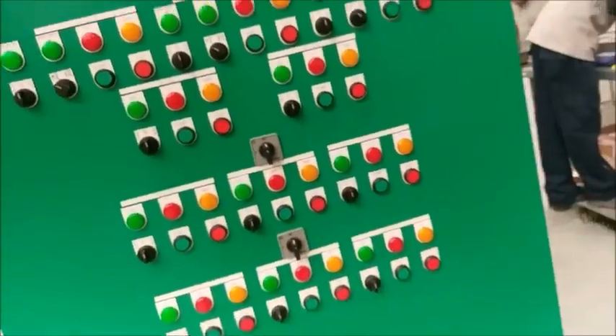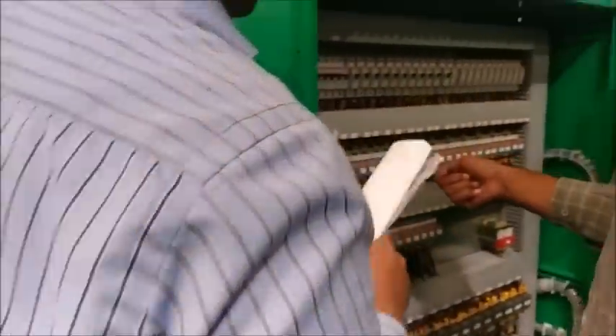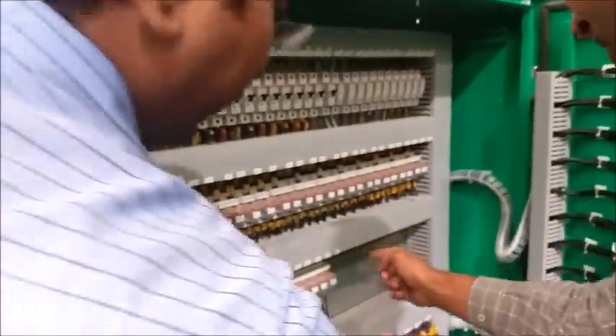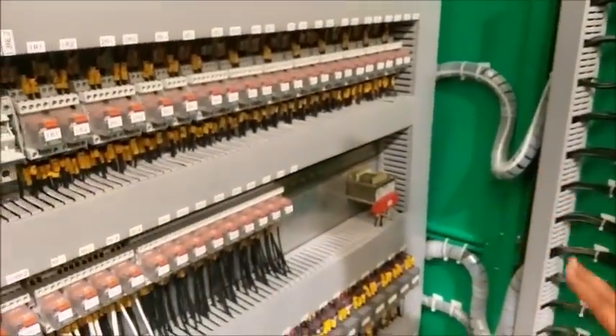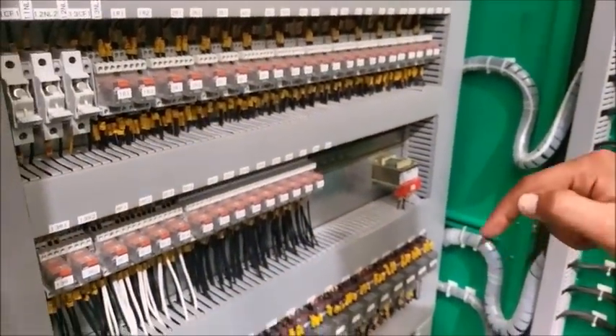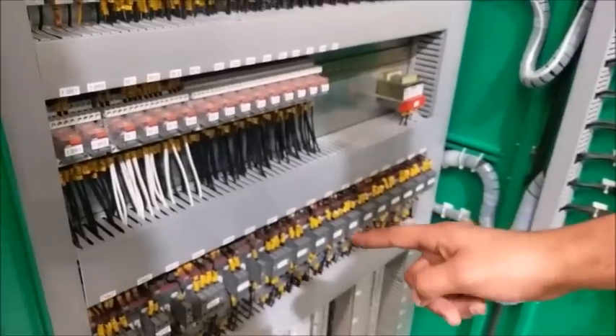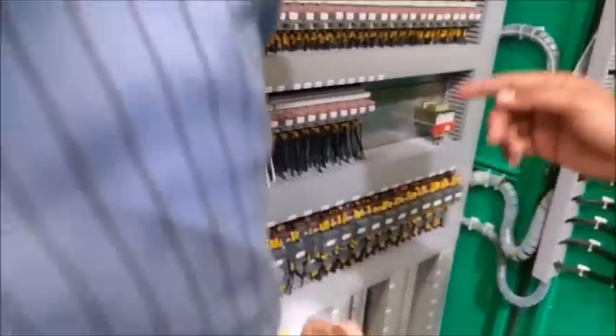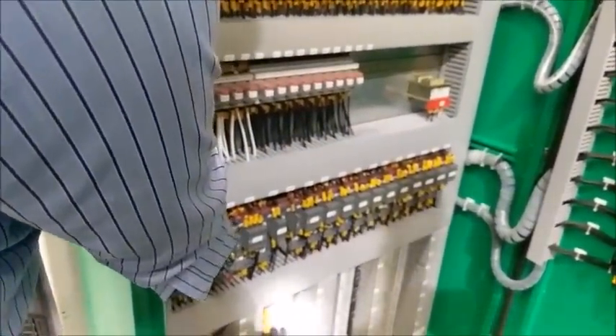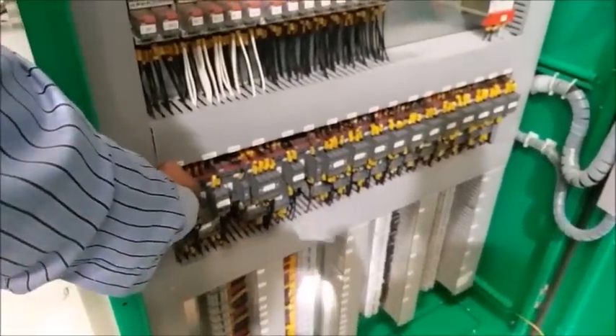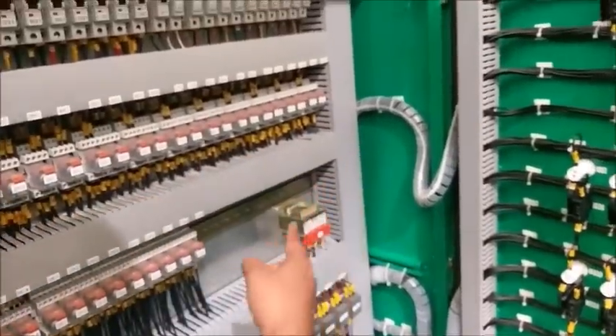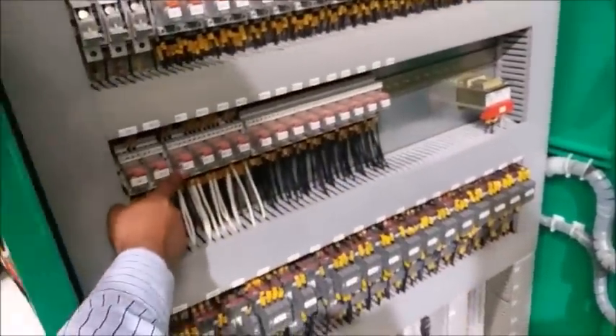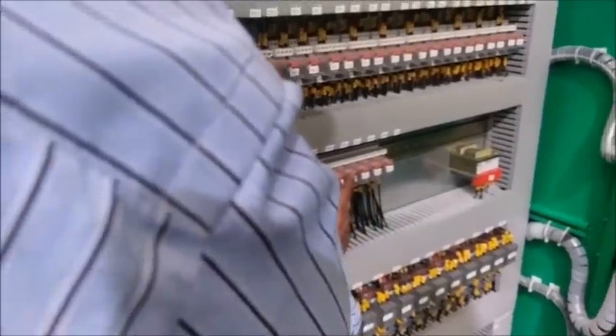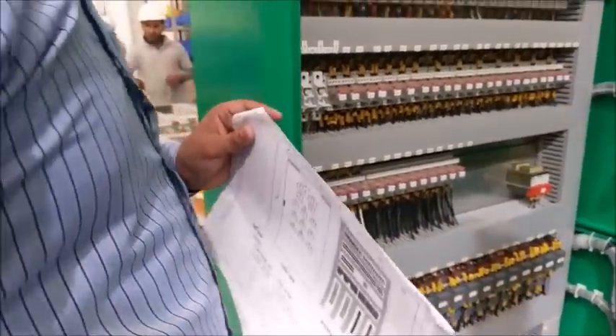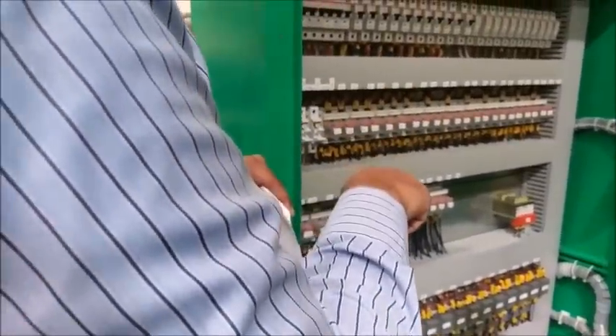And I have some connection for the fire alarm. Yes, that is also there. For the fire alarm, a 24 volt AC supply is required. And BMS. There must be a contactor for BMS and a contactor for the fire alarm. This is the RF1 fire alarm, and override is also there. This is for fire alarm override and the diffuse panels. If the fire alarm triggers, override closes this panel.